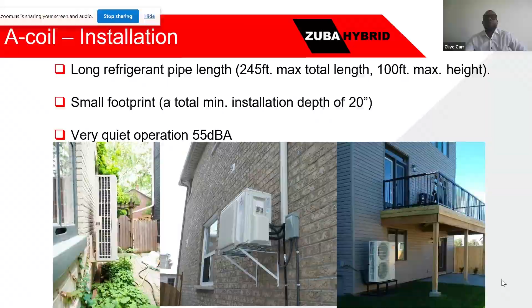You're not typically limited through pipe length and height limitation for residential installation, as you do have a maximum of 245 feet and a maximum height of 100 feet, which when it comes to residential application, whether you're doing a single family or a MURB low to mid-rise application, these piping lengths are feasible within those applications.